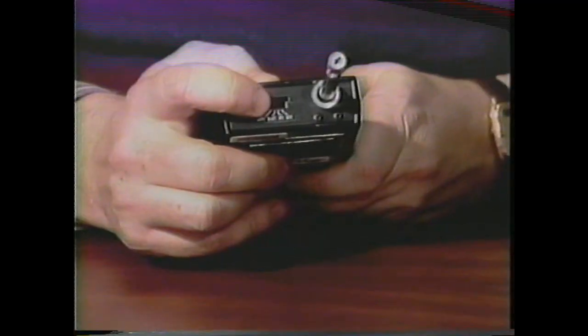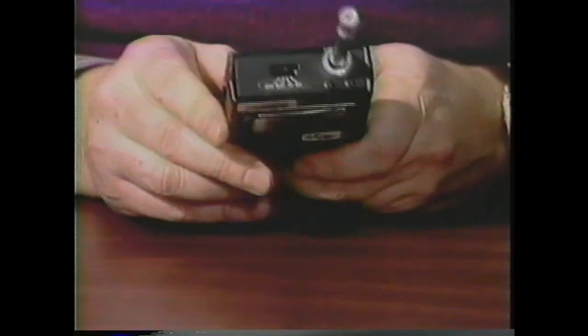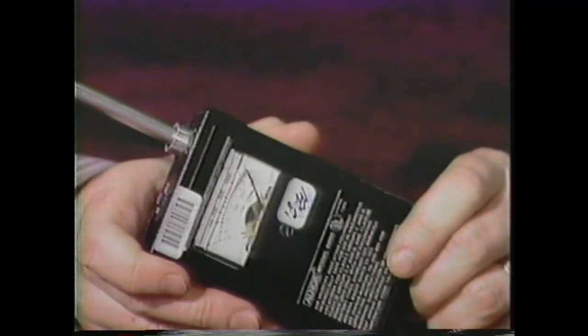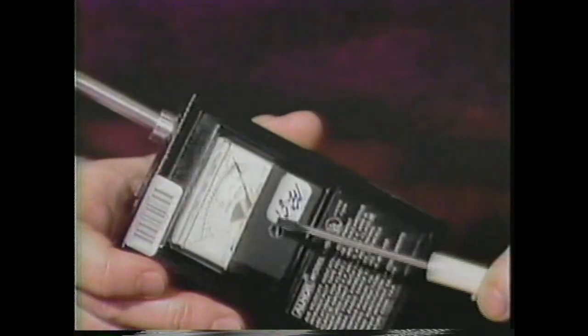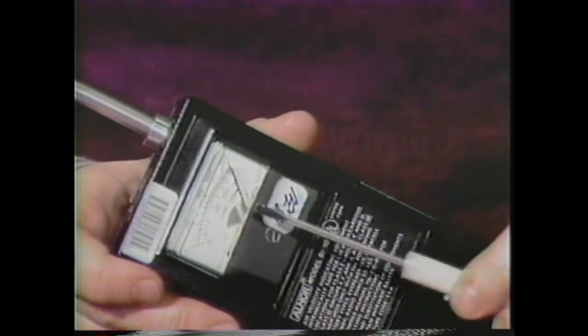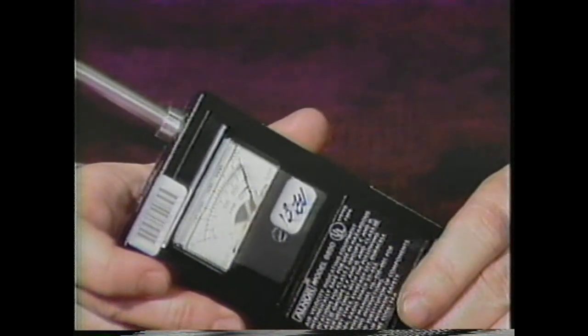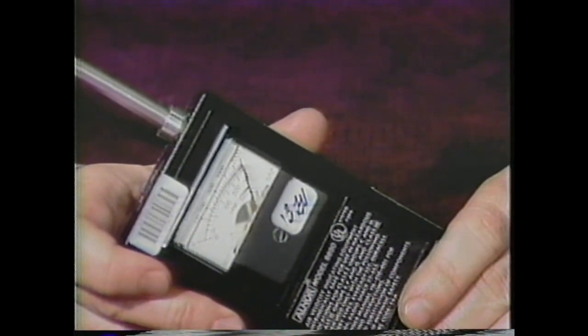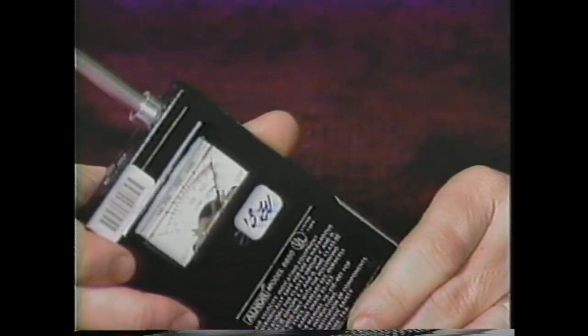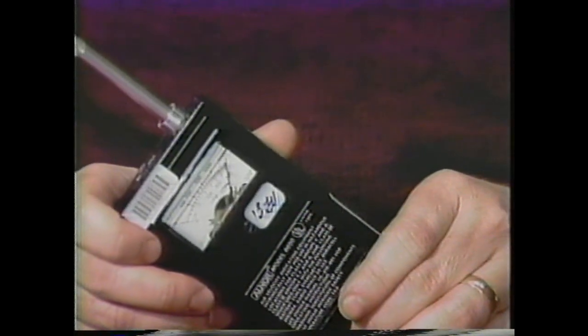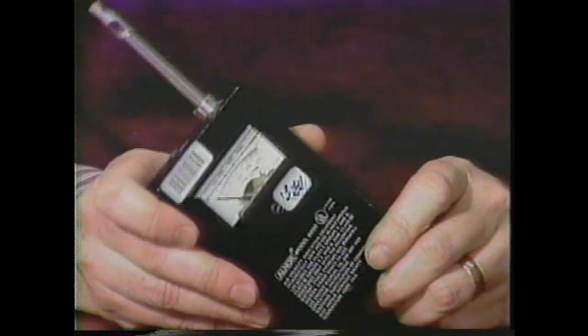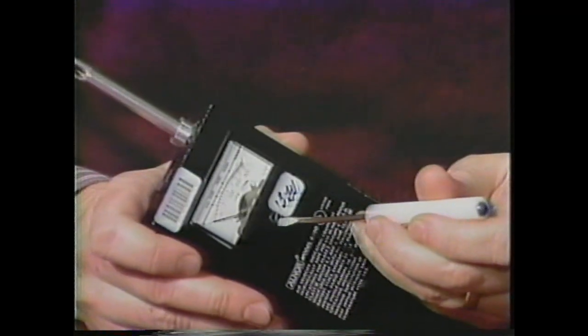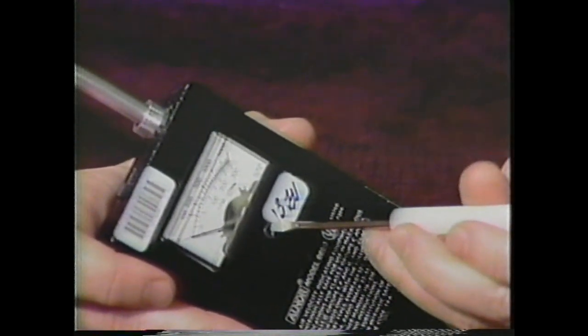To prepare the velometer for use, first check the 9-volt battery. You do this by sliding the switch at the top of the device to the battery position. Note the position of the needle on the instrument face on the right-hand side. If it is in the dark battery zone on the right-hand side of the meter, it has sufficient energy for use. After checking the condition of the battery, check to make sure that the device is mechanically zeroed. You do this by turning the unit off, and if necessary, using a screwdriver to adjust the needle on the face of the instrument so it reads 0.